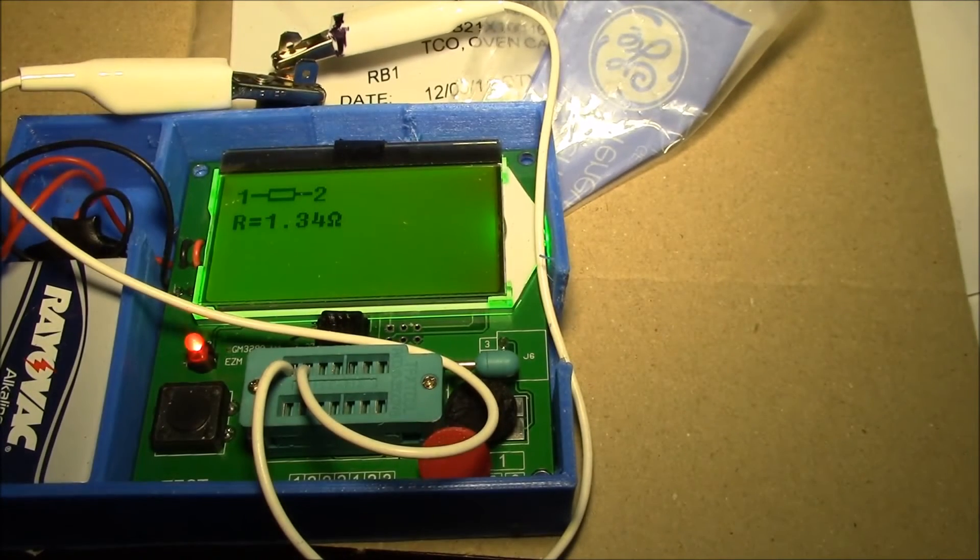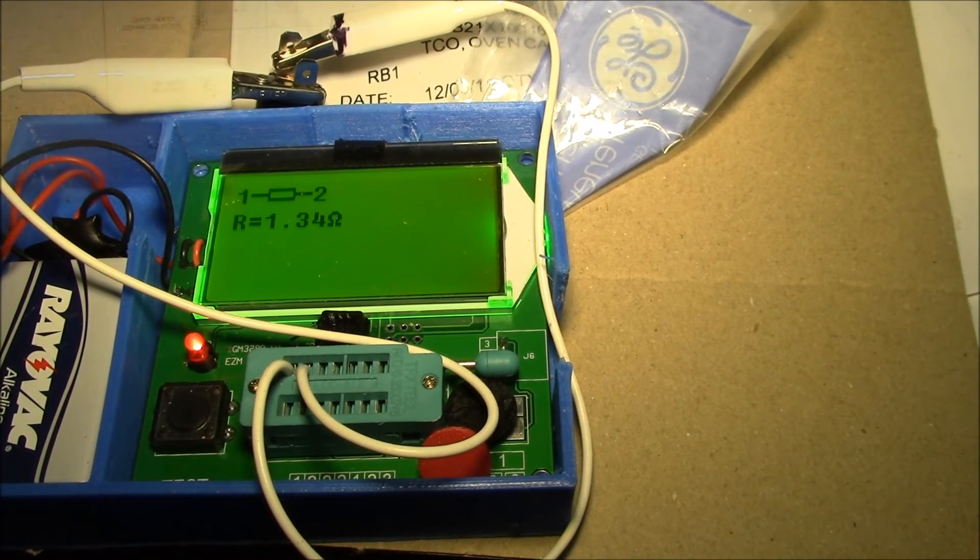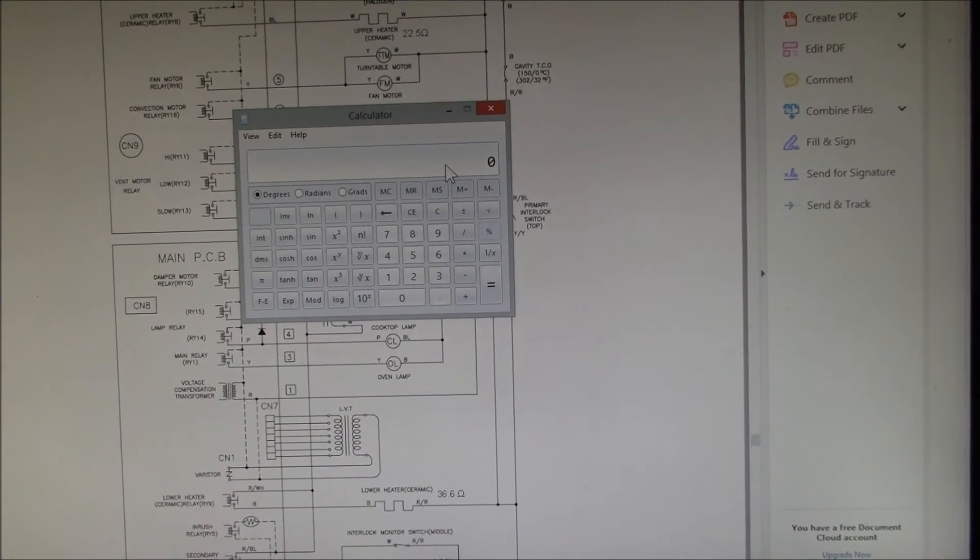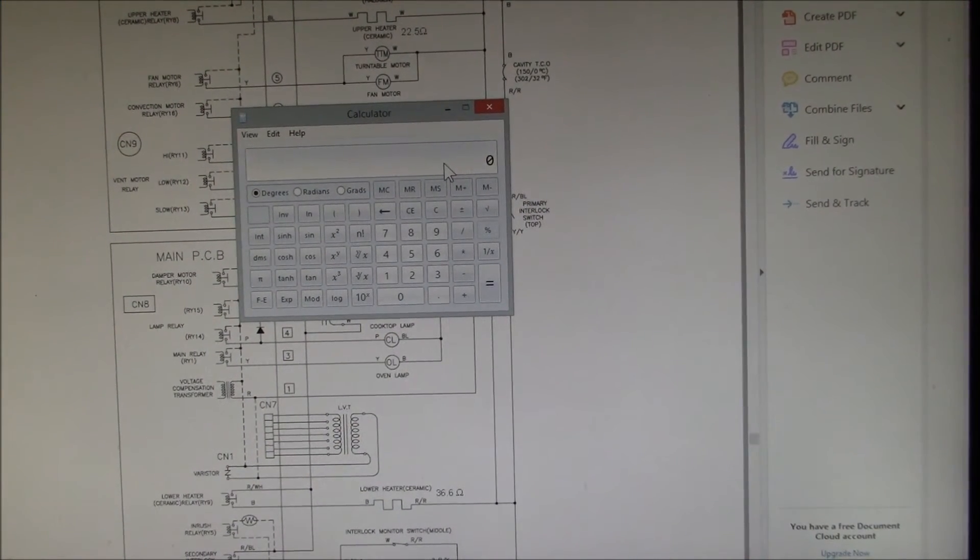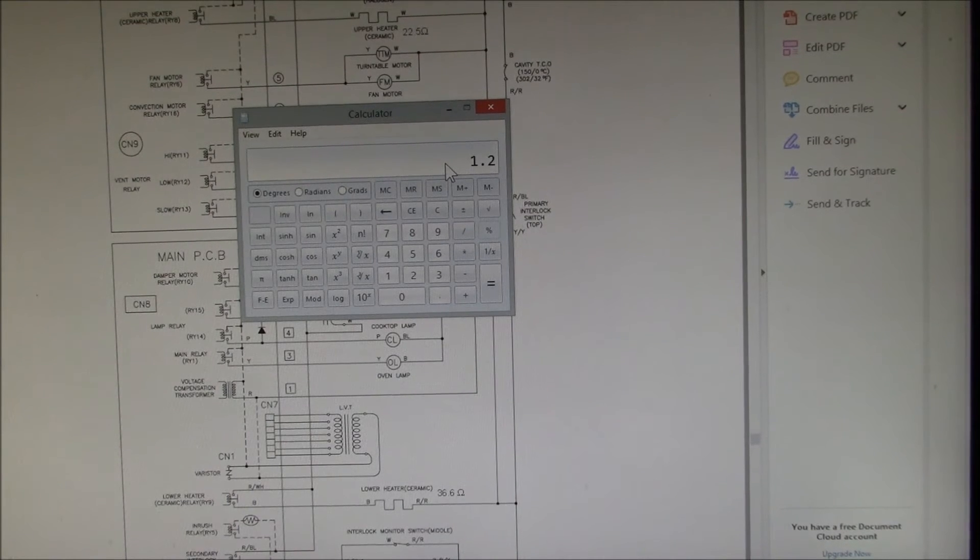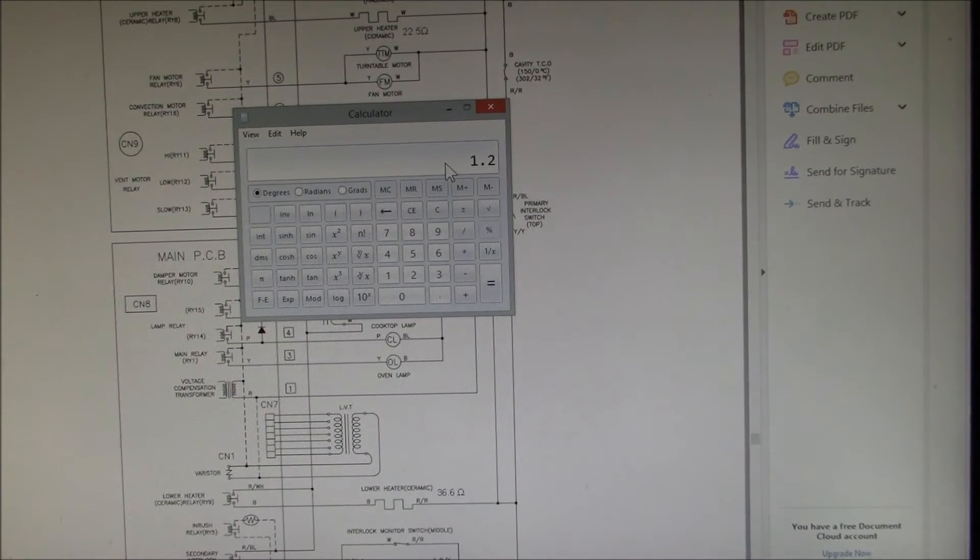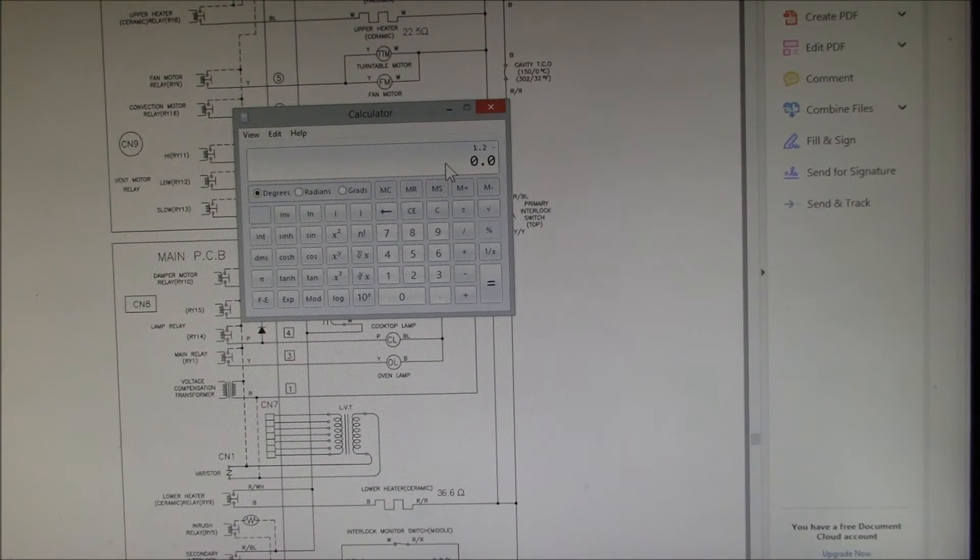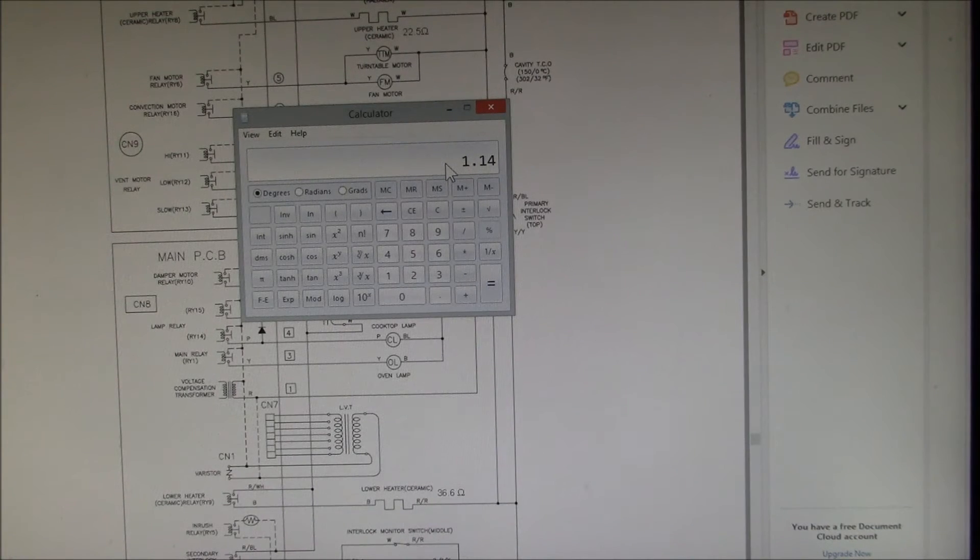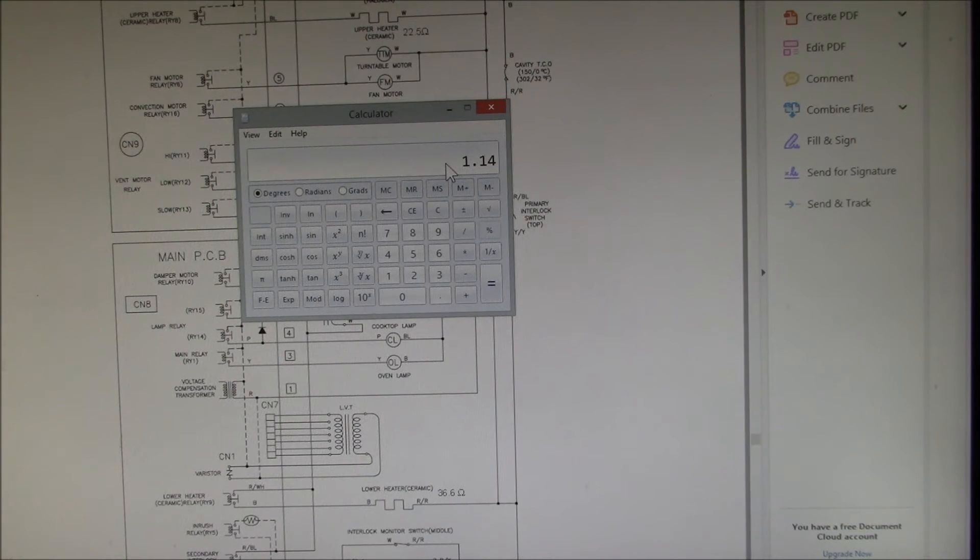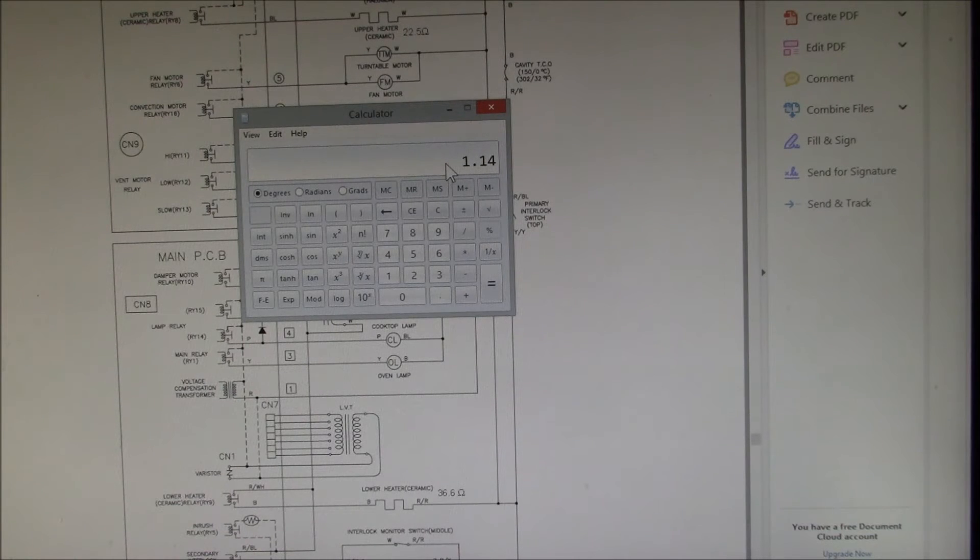Let's look at that on this screen again. We'll take the lower of the two readings, so we have 1.2 ohms on the meter minus 0.06, so that thermal cutout is 1.14 ohms.